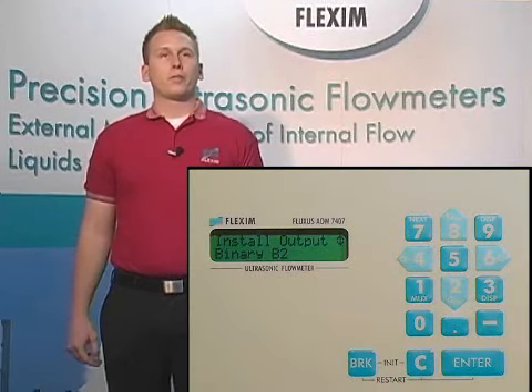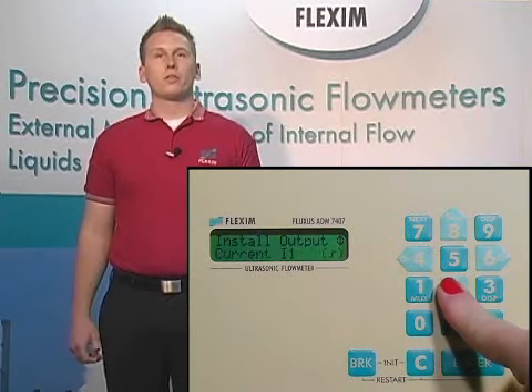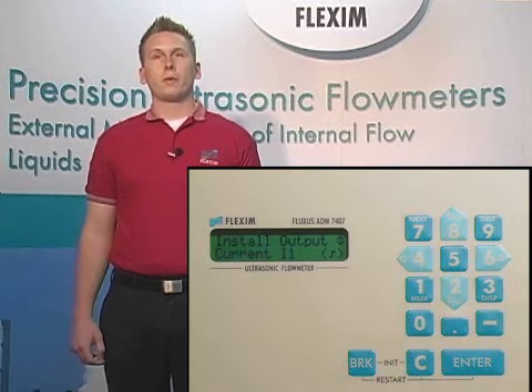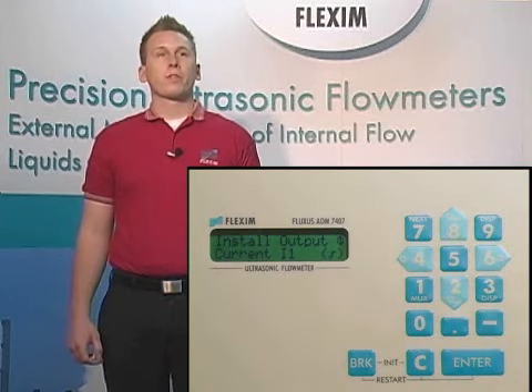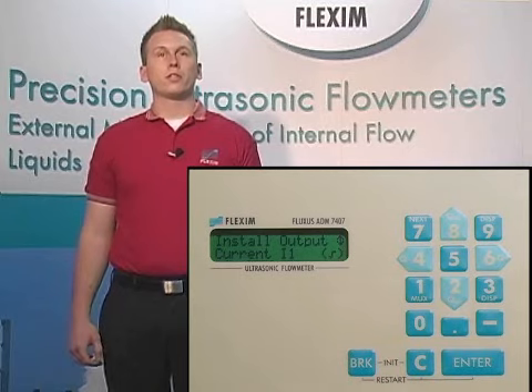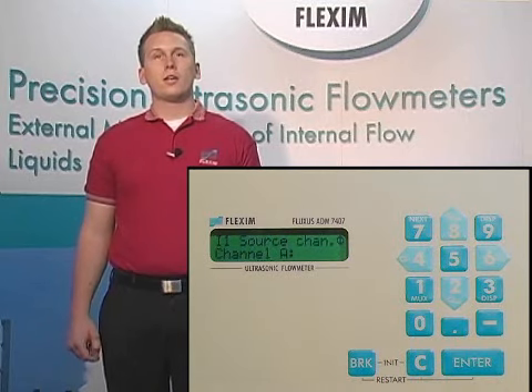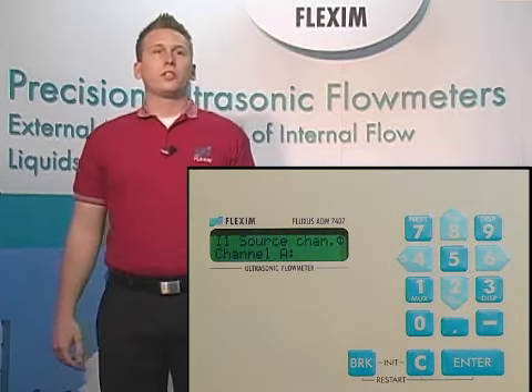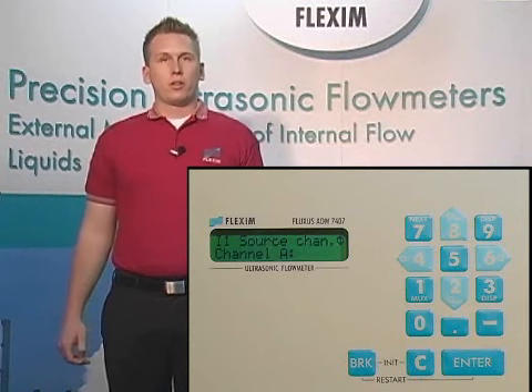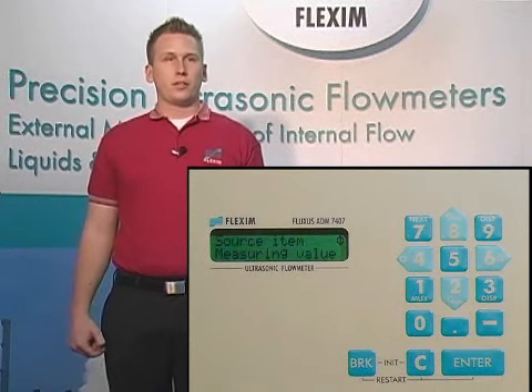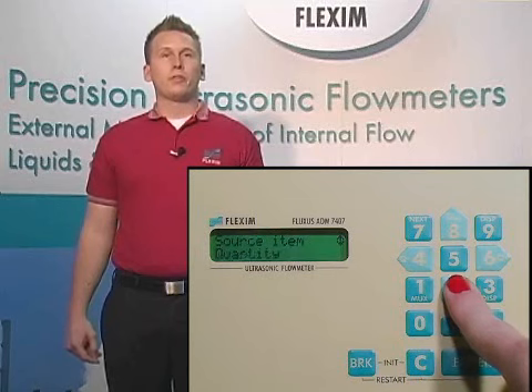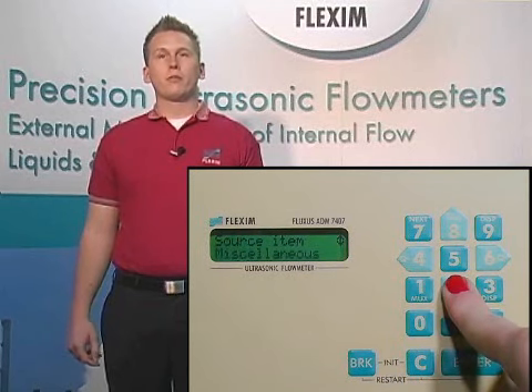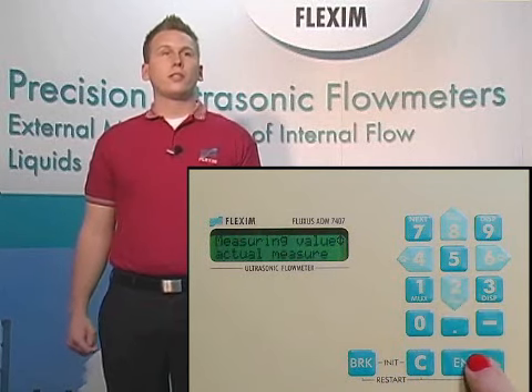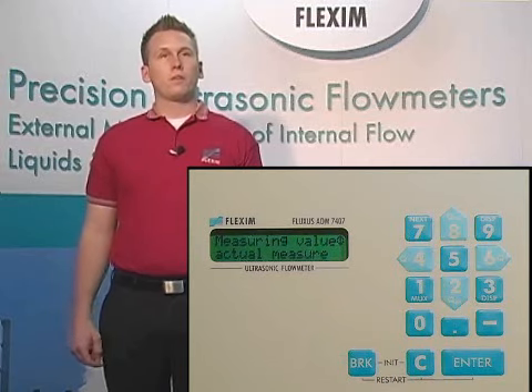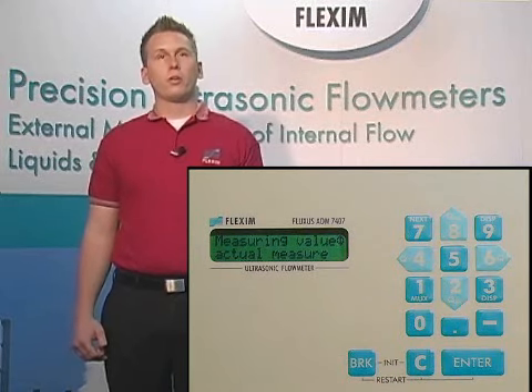For our binary outputs, we can set limits for alarm values or use them as pulse output to your PLC. But for now, we're going to assume you're using a 4 to 20 signal, and we'll choose I1 and hit enter. Choose the channel you'd like to set the output for. Channel A for us, and hit enter. Now we can scroll up and down for several options, the most common of which is measuring value. This allows us to output flow rate, heat flow, fluid velocity, our totalizer, or even sound speed.